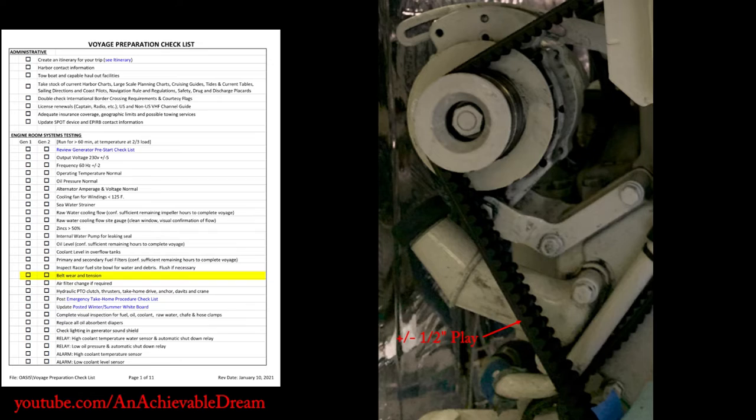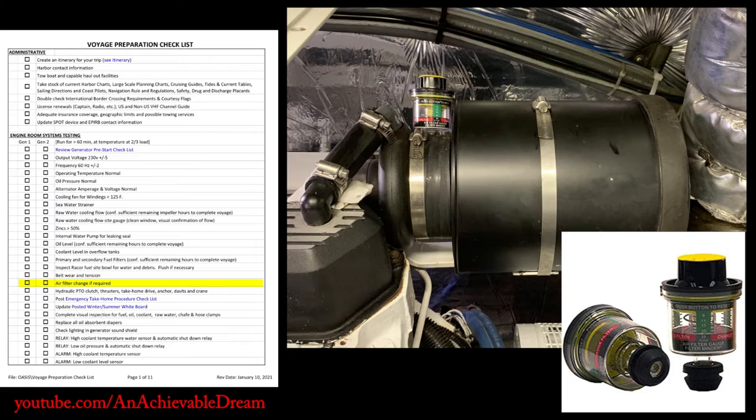Air filters are a bit like fuel filters. There is no way to tell if your filters need to be replaced without a vacuum gauge or a manometer. Do not attempt to clean a filter that isn't designed to be cleaned, and even then, closely follow the manufacturer's exact instructions. Ignore the old wives' tale about holding it up to the light, thinking that if you can see through the filter, it doesn't need changing. That is not the case.